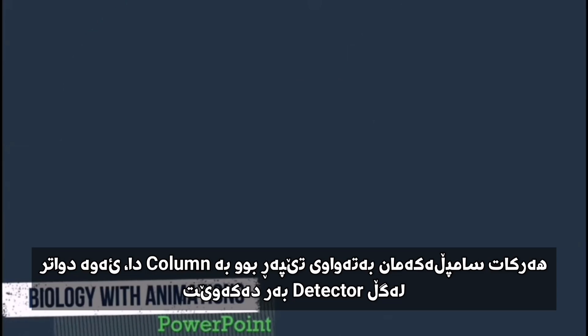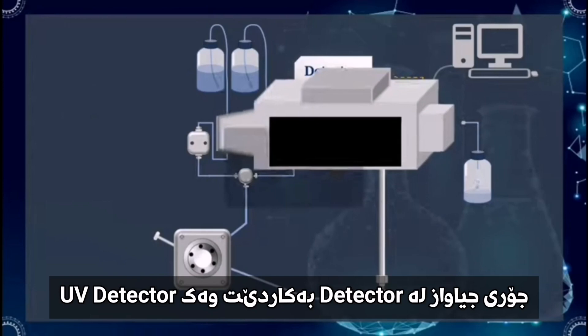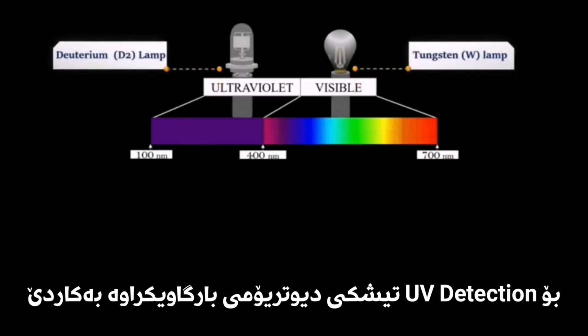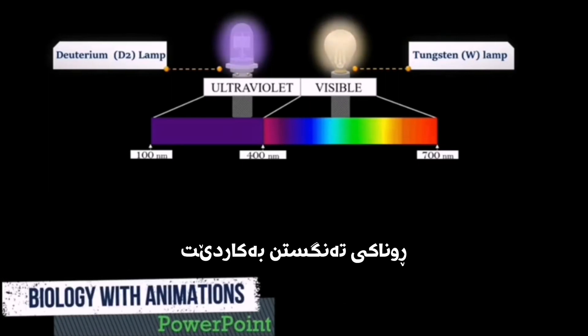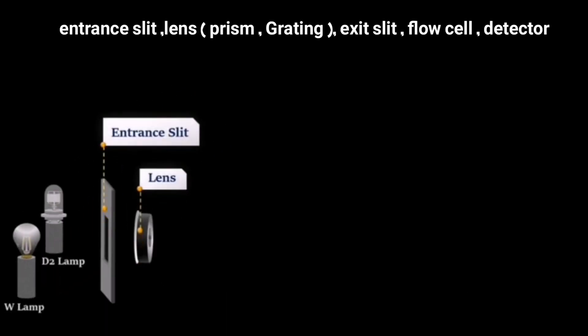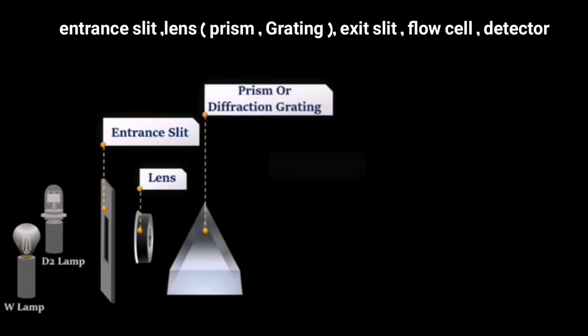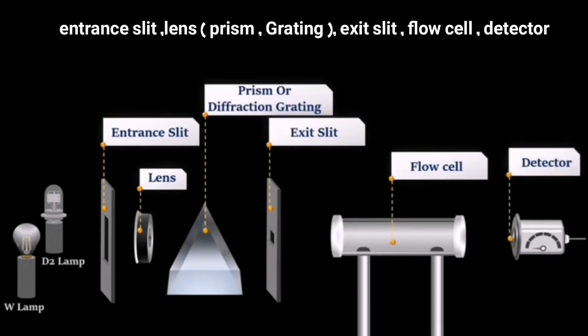As compounds elute from the column, they interact with the detector. Different types of detectors can be used, such as the UV-VIS detector, which shows an absorption spectrum in the ultraviolet or visible region. For the UV-VIS detector, a deuterium discharge lamp is used as a light source, and for component detection in the visible region, a tungsten lamp is used. In a UV-VIS detector we can also find an entrance slit, lens, prism or diffraction grating, exit slit, flow cell, and detector for absorption measurements.